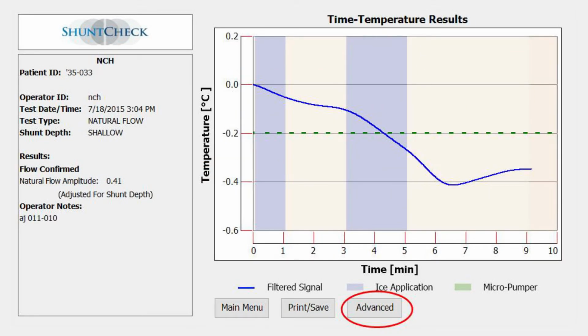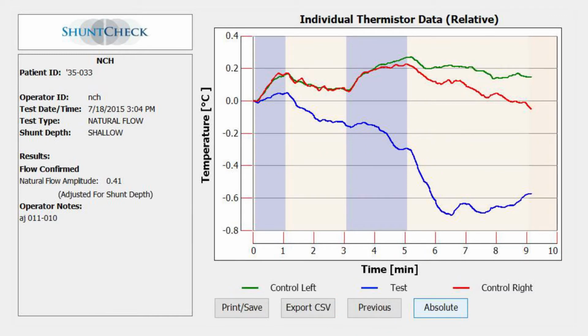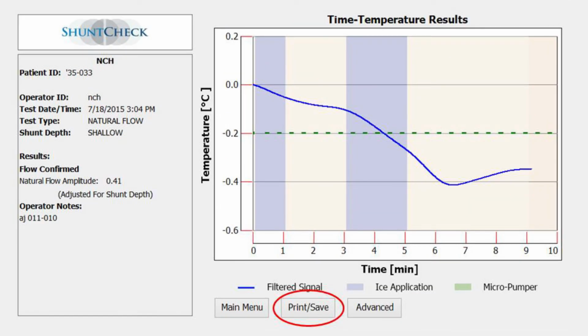If you click the Advanced button at the bottom of the results screen, you see a time temperature graph of the sensor's 3 temperature probes. The blue probe is over the catheter and tracks CSF temperature. Red and green are the right and left controls, which track ambient skin temperature. In this test, the controls show relatively constant skin temperature, while the blue test probe shows cooling due to CSF flow. The Print Save button allows you to print or save a PDF summary of the test result.